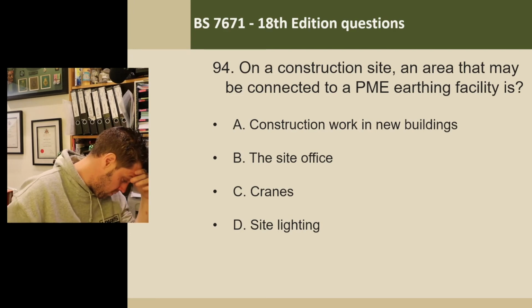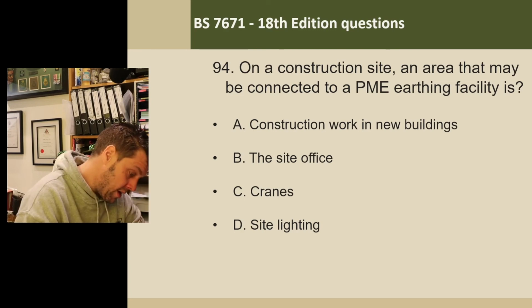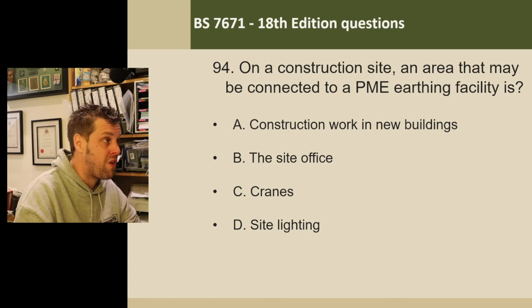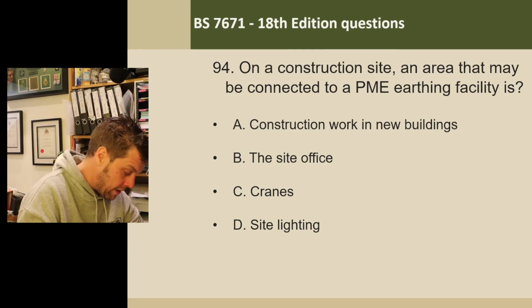Requirements for fault, general requirements. Placed out of reach - no. Circuit supply socket outlet - no. ADS, requirements for fault, PME - a PME earthing facility, it's regulation 704.411, which means it's referencing another reg in section 4.3.1.